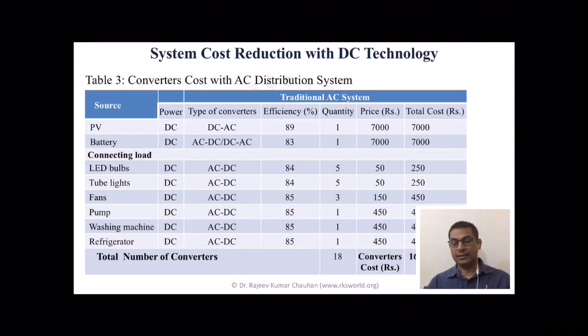So we can see that we require 18 converters for this autonomous small prototype system of the microgrid, and the cost of converters will be 16,300 Indian rupees. So with the DC distribution system, we not only increase efficiency, we also reduce the capital cost, as well as reduce the number of components. This means system reliability will increase, because with fewer components, the failure rate will be less.